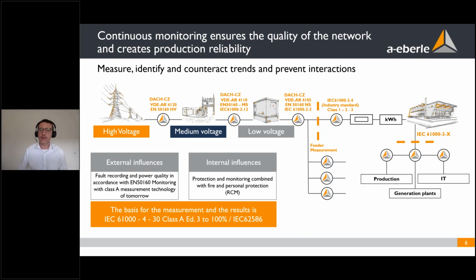A new field for us is the so-called feeder measurement. Mainly we install between interfaces, so between a TSO or a DSO, or between a substation, for example for wind farm or PV power plants, in low, medium or high voltage grid, to exactly monitor at this point of connection (POC) the power quality in general, and how, for example, a PV power plant reacts on earth faults. This is an interesting question, and our measurement technology helps to understand what happens and helps to keep the grid stable enough.